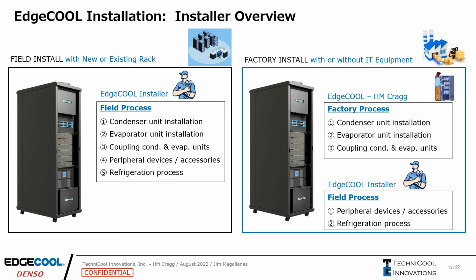And so all this installation that I just outlined can be done in the field with new and existing racks: condenser unit installation, evaporator unit installation, coupling the units together, attaching the peripheral devices and accessories, and doing the refrigeration process. That can be done by an HVAC contractor out in the field. Or we can work with HM Cragg on doing a lot of this process at their warehouse, at their site: condenser unit installation, evaporator unit installation, and coupling the units together. So this rack, pre-populated with the EdgeCool unit and maybe some equipment inside, whether it's UPS or IT equipment, we can ship directly to the end user. Once it's shipped there, they can roll it into place, get an HVAC contractor just to set up the peripheral devices, whether it's the condensate pump or the ducting, quickly do the refrigeration process, and have that operating in a short time.